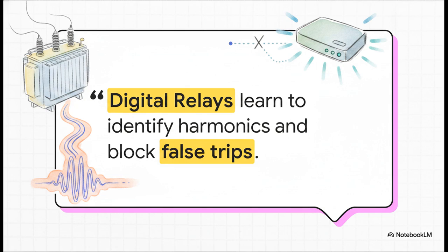harmonic frequencies. That means 100 or 120 hertz, depending on your local grid. And modern digital relays are smart enough to constantly listen for that specific frequency. When they detect it, they realize, oh, okay, it's just a startup surge, not a real fault, and they actively block the trip command. It's such a clever way to keep the grid online.